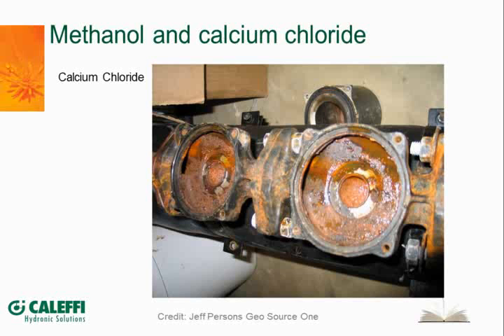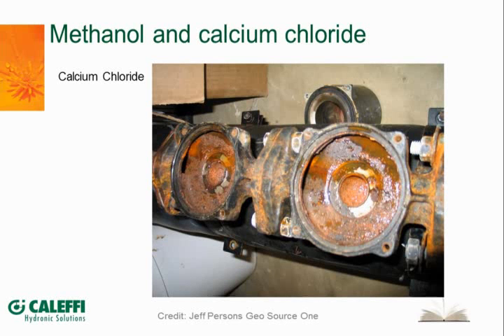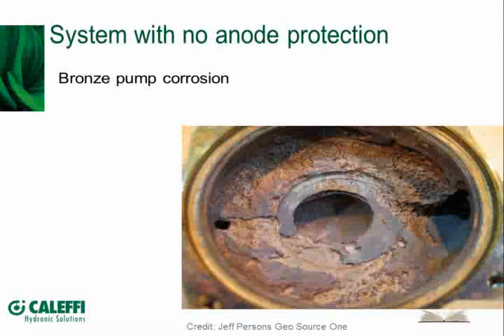This particular flow center chewed up, I believe, six circulating pumps in about a two-year period, just from corrosion and failure. The corrosion products would get in around the wet rotors and lock the pumps up solid. It was quite the problem until it got corrected. Correcting it meant flushing the loop with DI water several times to get it cleaned out, then replacing that fluid with an inhibited propylene glycol solution. It's very expensive — not something you want to have to go through.